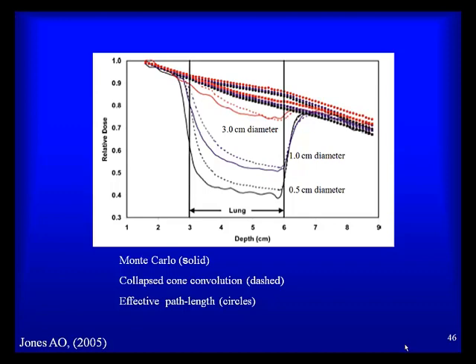A figure from Jones demonstrates that in a stylized water-lung-water phantom, the difference between Monte Carlo, convolutional superposition, and pencil beam is dramatic — significant as a function of beam aperture at 3 cm, 1 cm, and 0.5 cm. The pencil beams almost fail to account for the presence of the lung heterogeneity, whereas convolution superposition and Monte Carlo do a good job accounting for the heterogeneity.